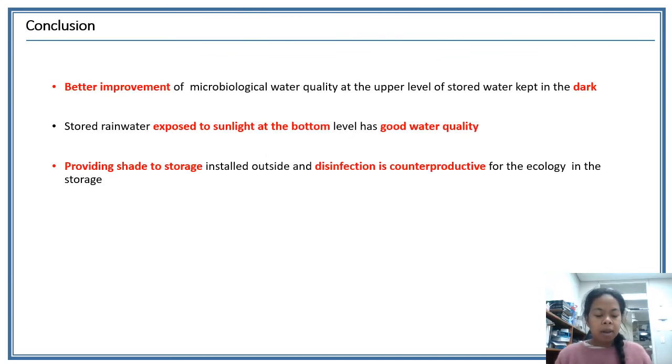To sum up, the microbiological water quality improves during the storage, especially when the storage is kept in the dark. For storage exposed to sunlight, it's better to provide shading and not disinfect because it's counterproductive for the ecology in the storage.